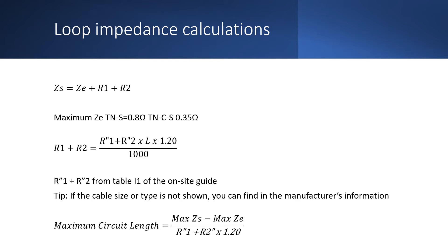It is necessary to use a factor of 1.2 to allow for the fact that the impedance of the circuit will increase when under load. So for the same reason that we subtract 20% from the maximum ZS in table 41 when we're testing a circuit, when we're designing a circuit from scratch we need to use a multiplier to add that 20%.